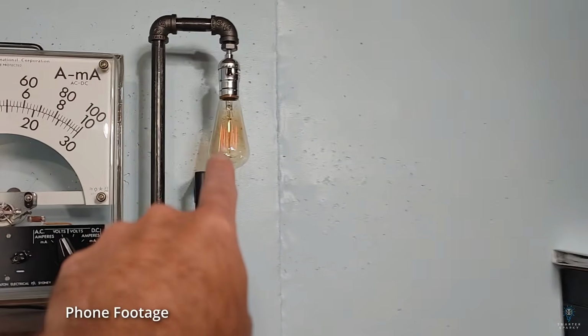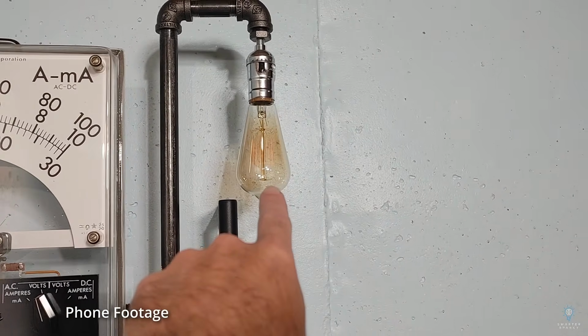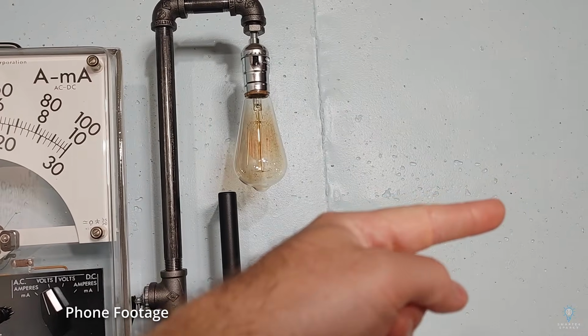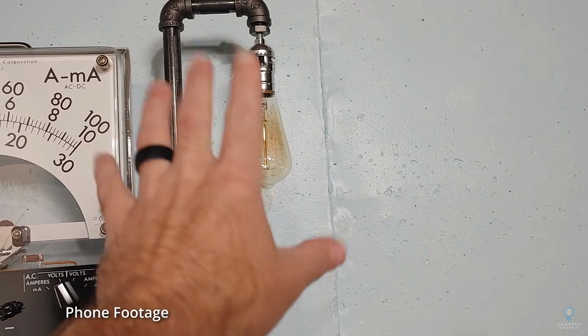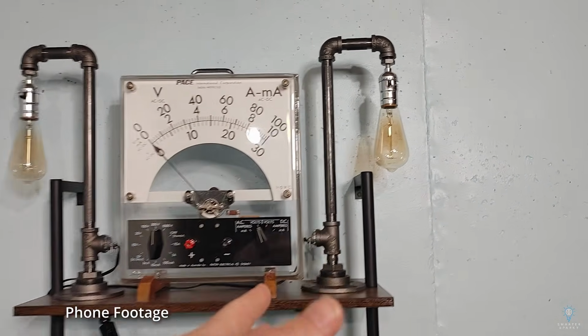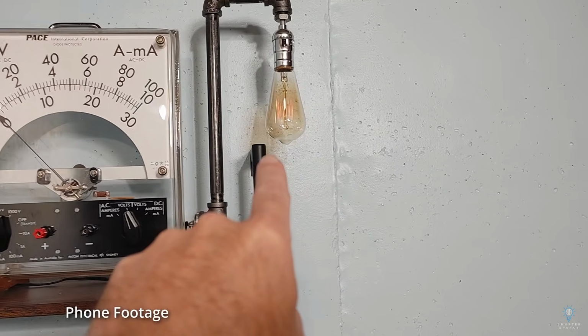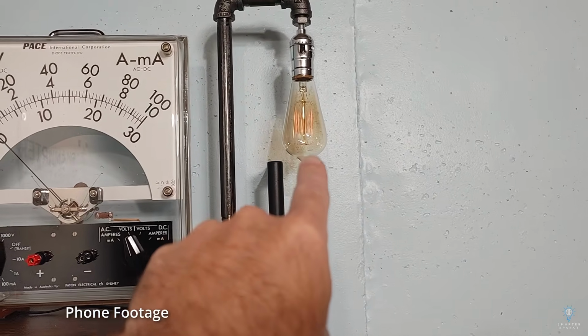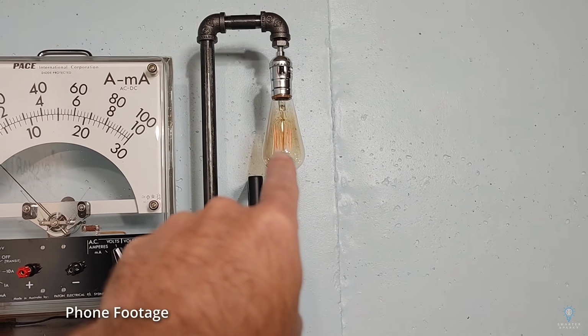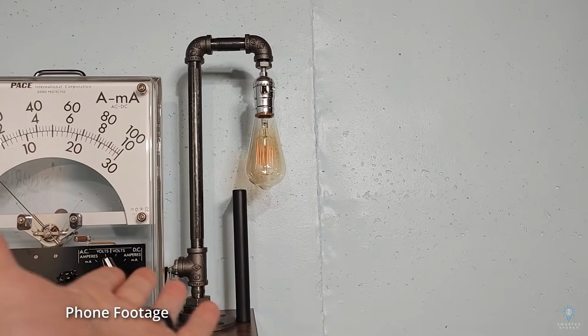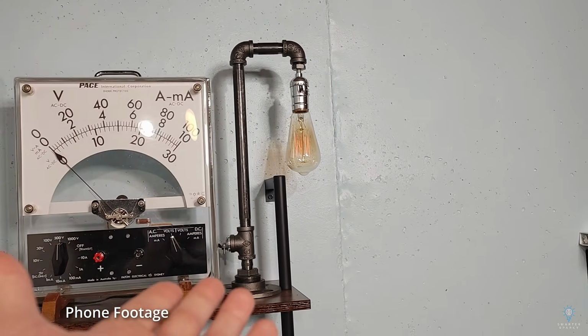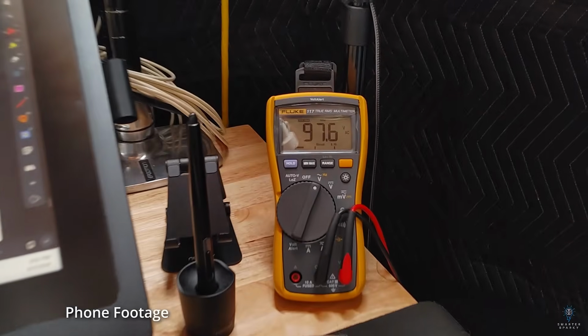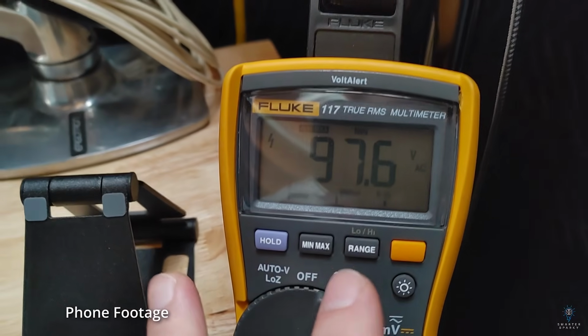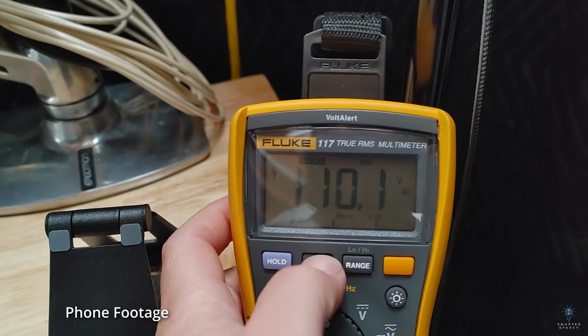And look at this light bulb now. It's dim. Oh, there it just really dimmed, and I just heard the sump pump kick in. So that thing just dimmed way down. It's pretty cool. We caught it on camera there. But then we wait, and this starts to get brighter again. And that's very, very indicative of a loose neutral. So I am very convinced there is a neutral issue going on here in this house.